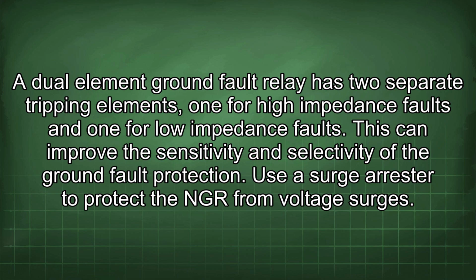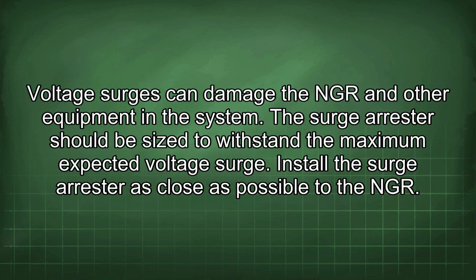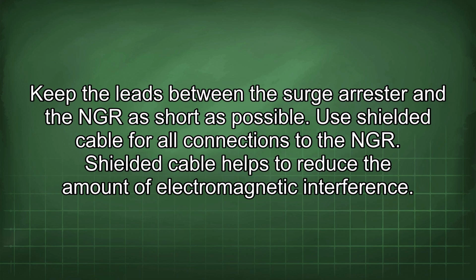Use a surge arrestor to protect the NGR from voltage surges. Voltage surges can damage the NGR and other equipment in the system. The surge arrestor should be sized to withstand the maximum expected voltage surge. Install the surge arrestor as close as possible to the NGR. Keep the leads between the surge arrestor and the NGR as short as possible. Use shielded cable for all connections to the NGR. Shielded cable helps to reduce the amount of electromagnetic interference.